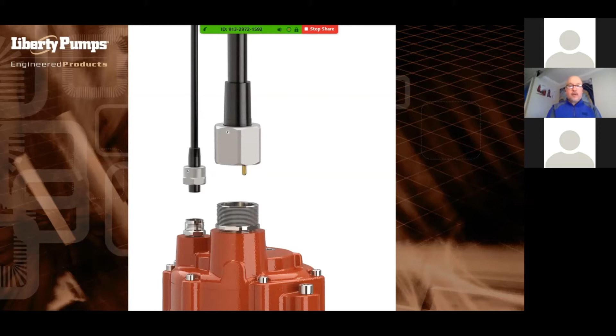A few other specifiable features and a unique design. These are patent pending designs. One is mid-therm cooling. This provides enhanced motor cooling by increasing the volume of oil and expanding it into the middle chamber. I have a couple slides coming up showing some other manufacturers' designs, but basically what we're showing here is that this area down in the middle chamber is completely open, or 70% open cavity with about a 30% cavity where the seal rides in the seal sensor probe. So this is not an isolated chamber. The oil is able to circulate from top to bottom. When that pump is running, the liquid it's pumping is generally cooler, and it's dissipating the heat from the oil and the motor to help that motor run cooler. And of course, temperature is what usually deteriorates motors. Temperature is what deteriorates motor insulation over time. So that is available on all the dual seal pump designs.